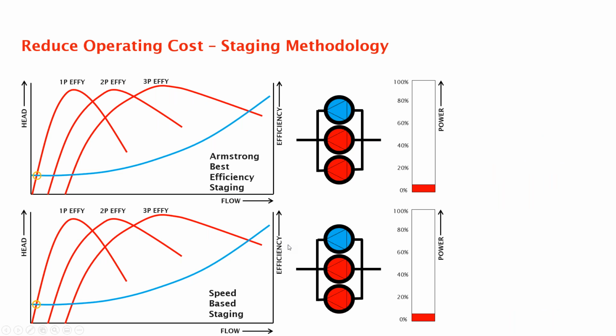So let's take a look and see on a chart. Now this is an active chart. It's not very quick, but I'll show you real quick here. On the top, we have 3 individual pumps that are built into a design envelope for efficiency staging. And down below, we have 3 pumps based on speed staging. Speed staging will increase, and you'll see that we cross a point here between the first and second pump. This is where the second pump will initiate start for the best efficiency staging. But the lower section, you'll see it's going to continue because you still have this much speed to take up out of that motor. And right now, you'll see that the percentage of power, this is where we want to pay attention. The curve is identical.